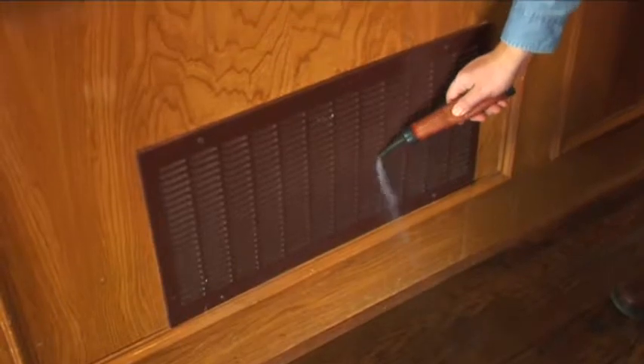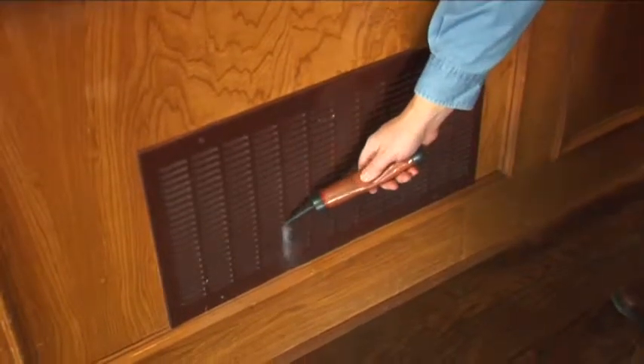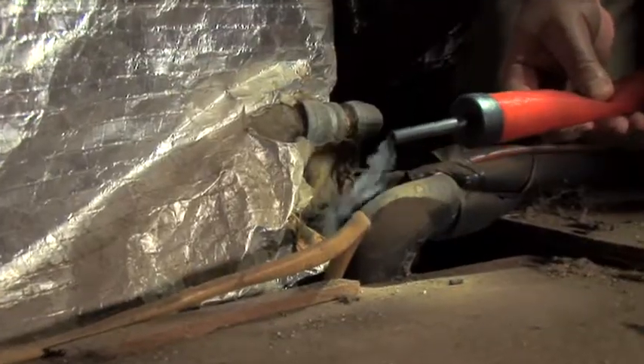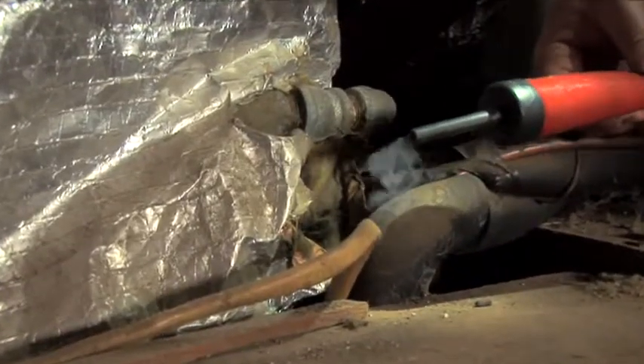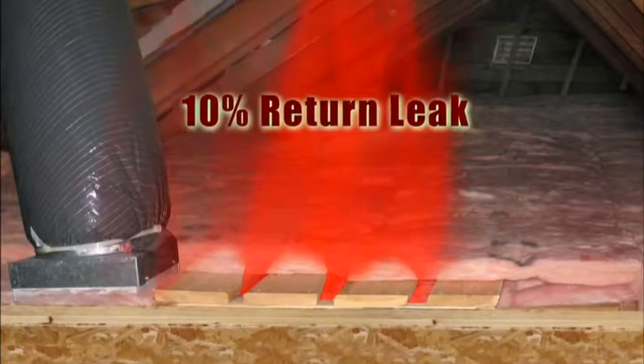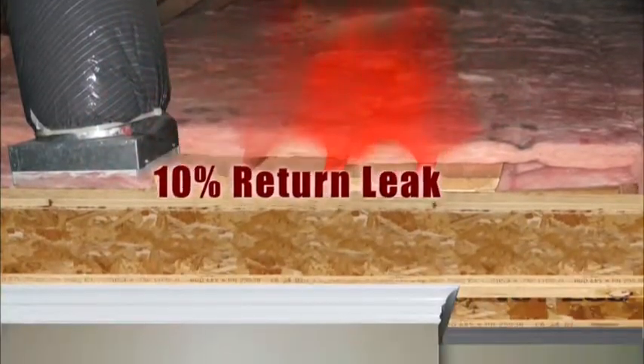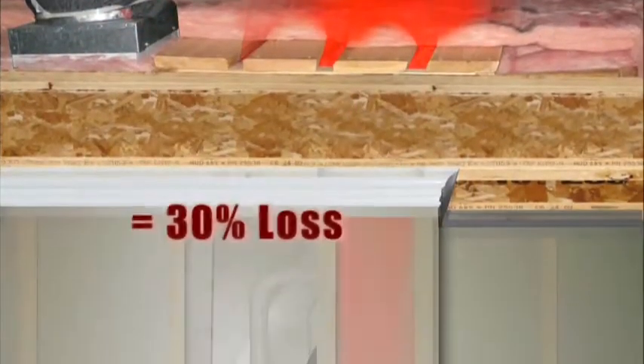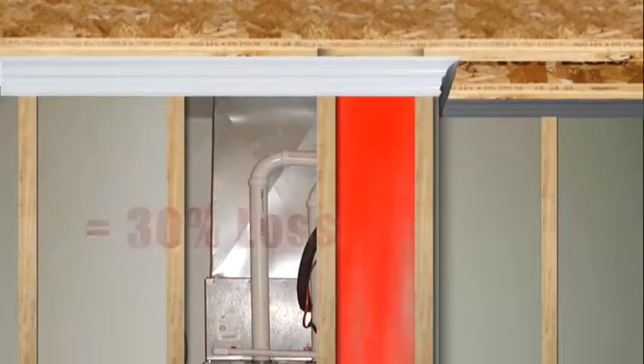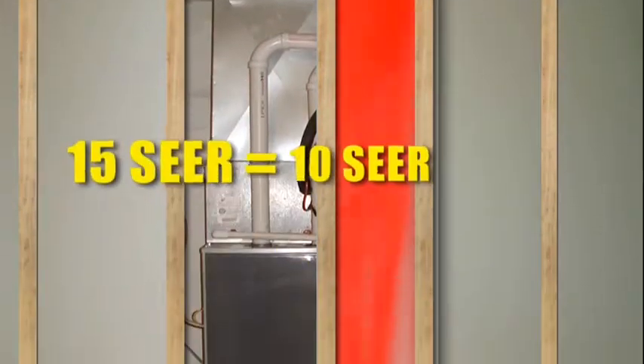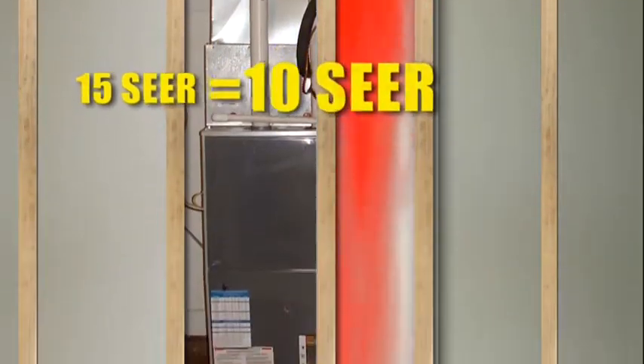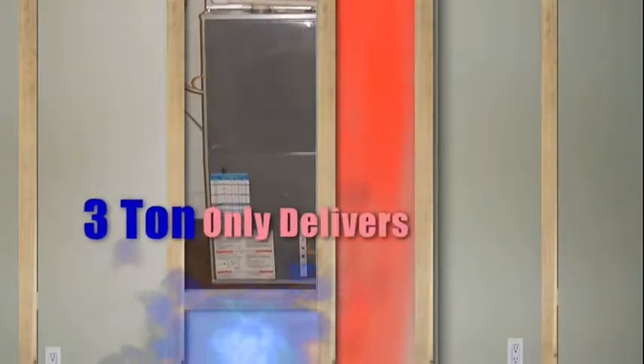Another large problem is that builders save money by using wall and floor cavities to carry the return air back to the equipment instead of actual ductwork. Unfortunately, they leak like crazy, and many suck air in from hot attics. Researchers have found that if just 10% of the return air comes from a hot attic instead of the house, it cuts the air conditioning efficiency by a full 30%. That means a 15-SEER air conditioner only works like a 10-SEER, and a 3-ton air conditioner only delivers about 2 tons.